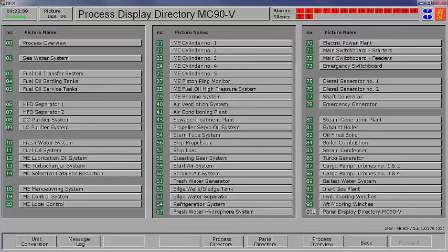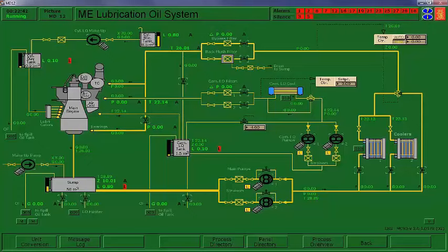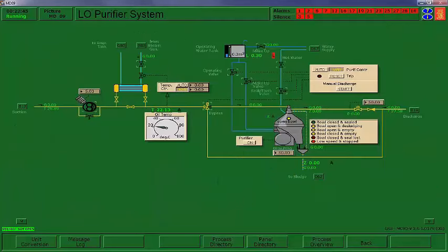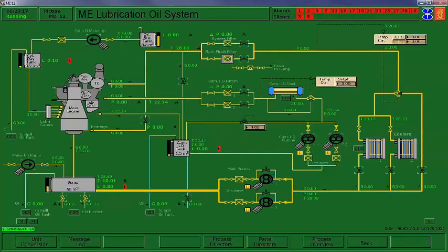All right, so let's go back to lube oil. We're going to line up to the lube oil separator. We can go ahead and start the pump up, and we're going to set its variable speed drive for 25%. Wait until we get a flow. And then we're going to use a set point of 85°C. We're going to put the temperature controller in automatic and go ahead and put on the steam. So what we're doing now, and you can see the flow from and back, we'll be using that to heat up the main engine sump.